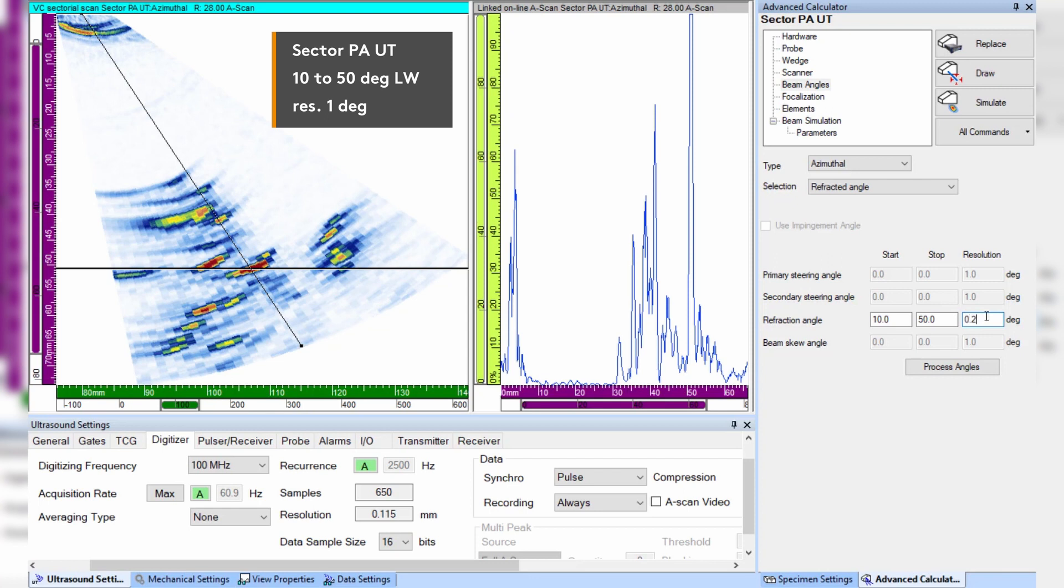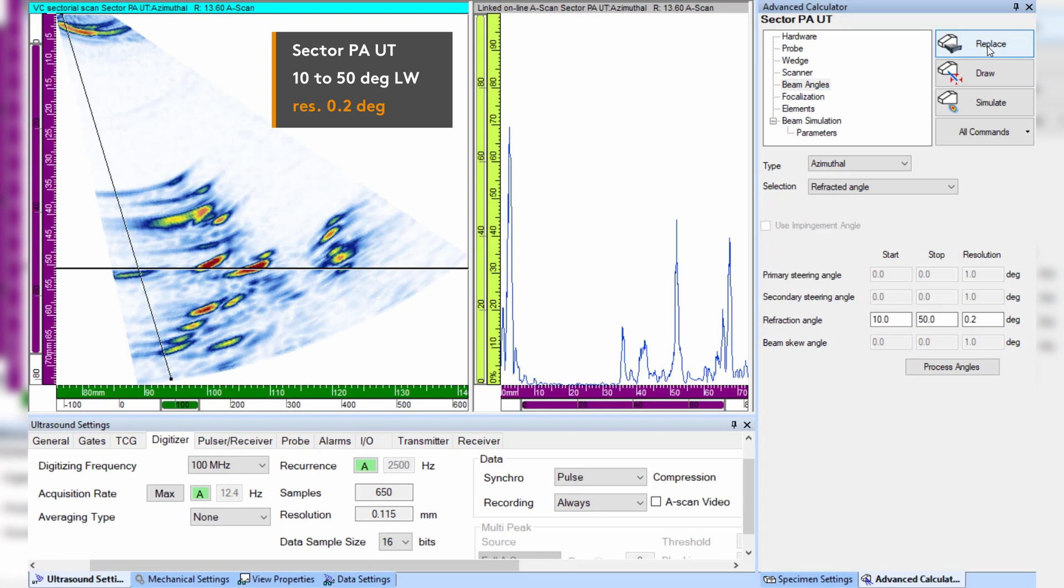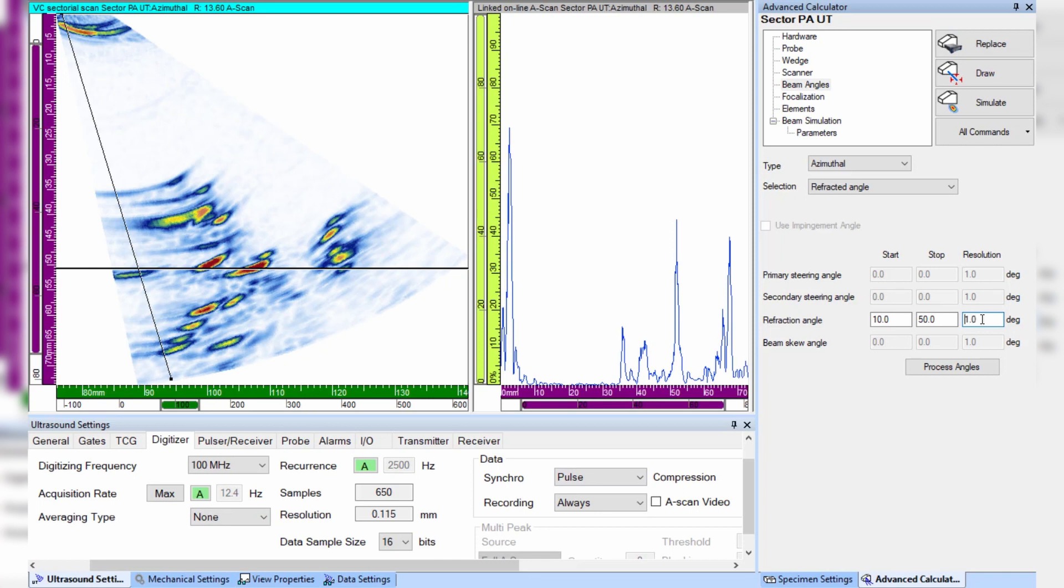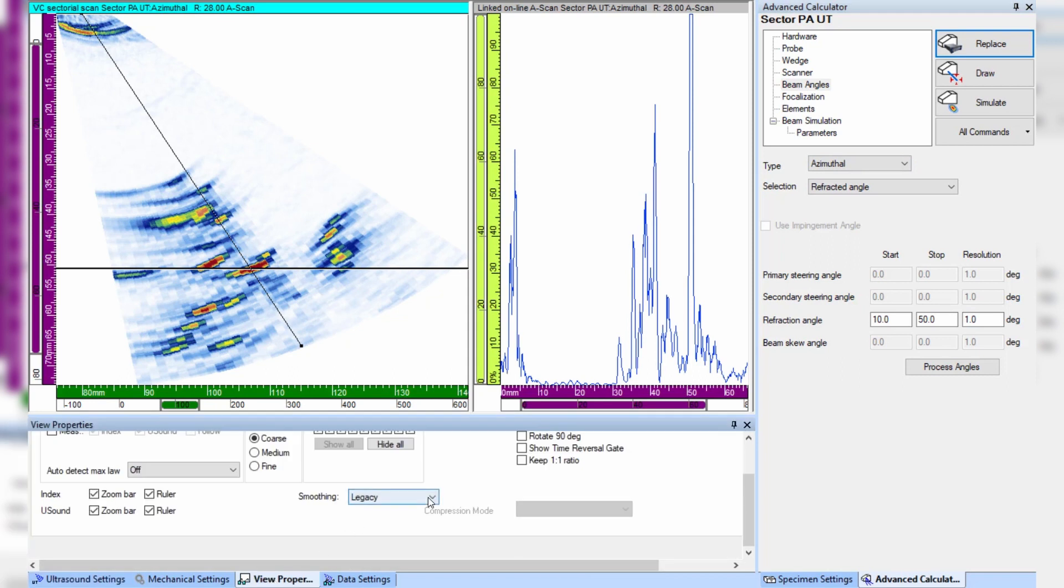Unfortunately this also reduces the maximum acquisition rate by a factor of 5, so we go back to a one degree resolution and instead activate the new sectorial smoothing algorithm. We keep the same high quality image and we have regained the original acquisition rate.